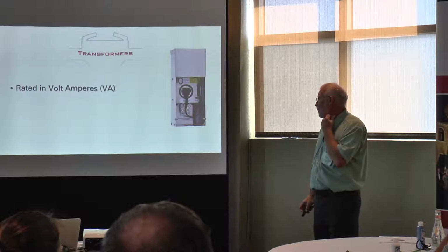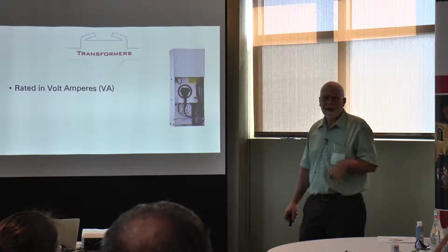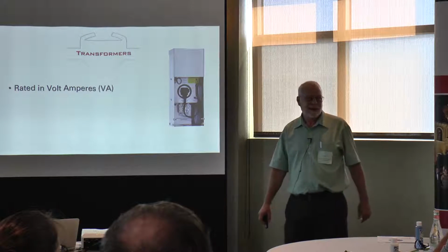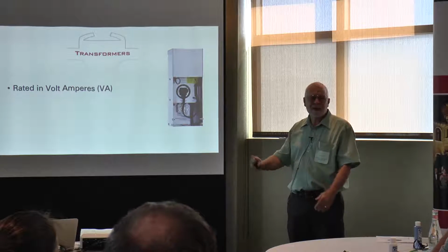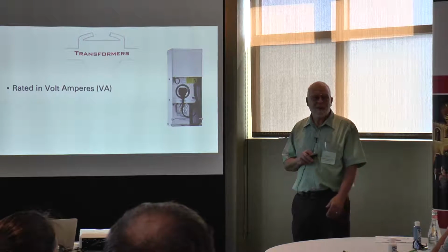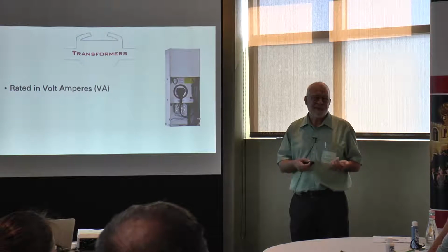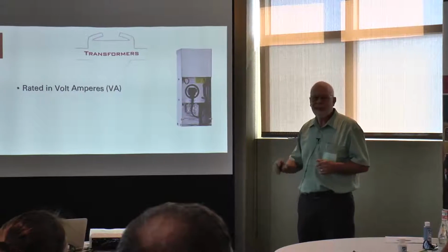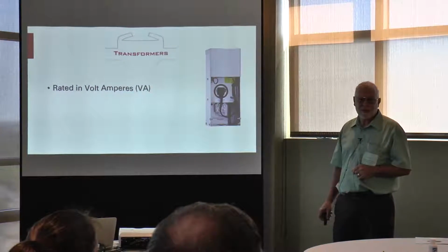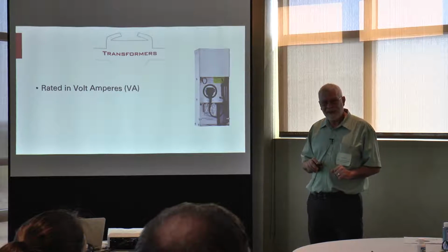Transformers. Okay. We lovingly refer to these things as a 300 watt, a 600 watt, 150 watt. Really though, transformers are rated in voltamperes. And when you're sizing your system, the VA, or the voltamperes of the lights, matching up with the VA capabilities of the transformer, that's what's important.